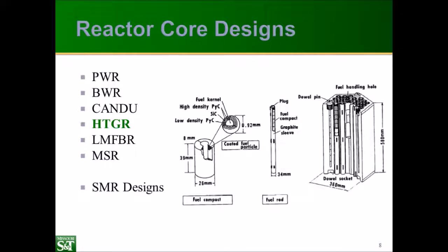So it requires a lot of flow recirculation, and there's a large temperature difference between the coolant and the fuel matrix. Now, this system operates at 900 degrees Celsius or higher, which is good because it provides higher efficiency, and the heat can be used for process heat for other processes. However, there are some materials challenges associated with this system.